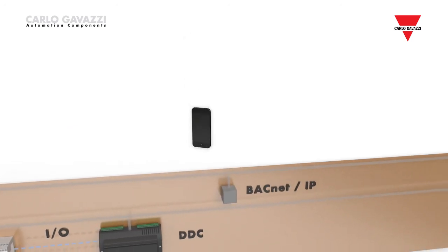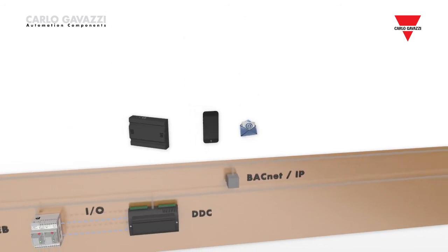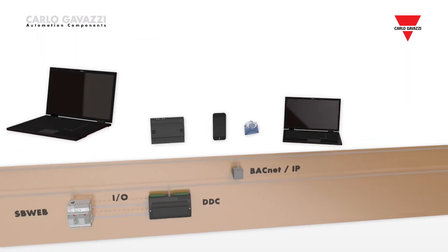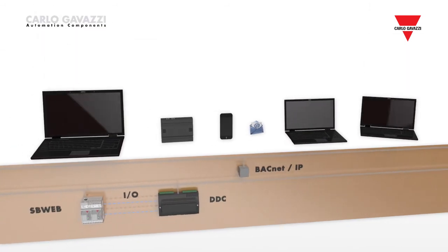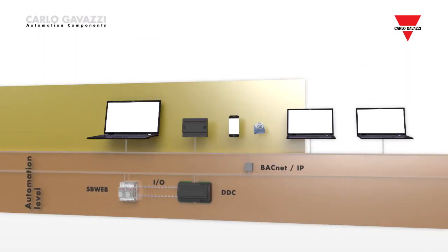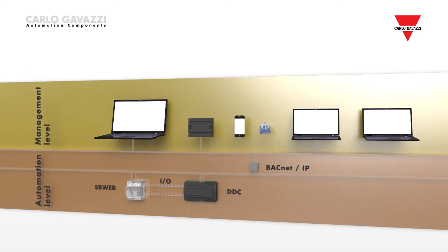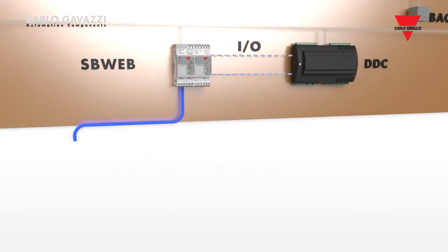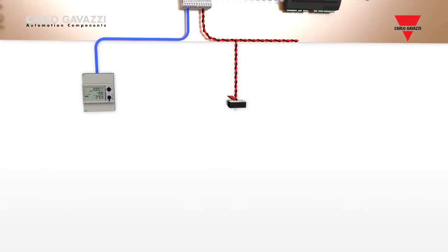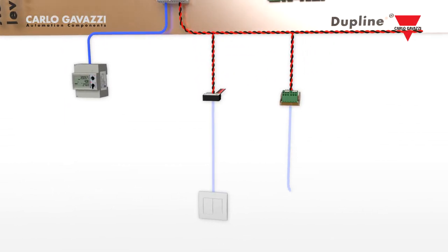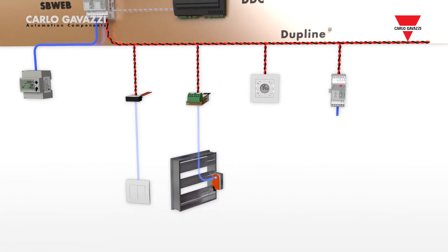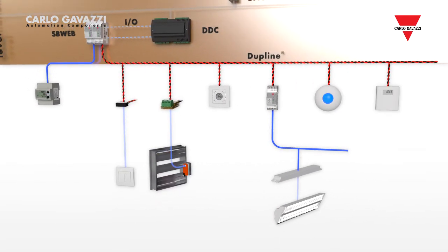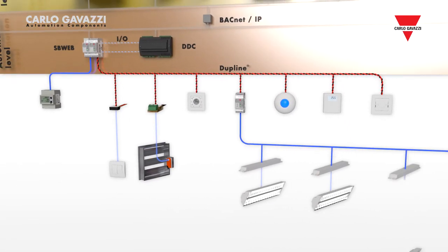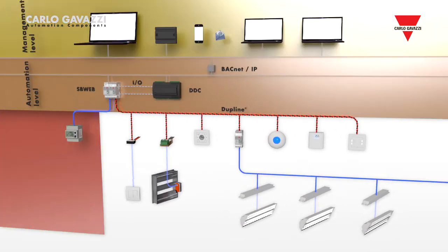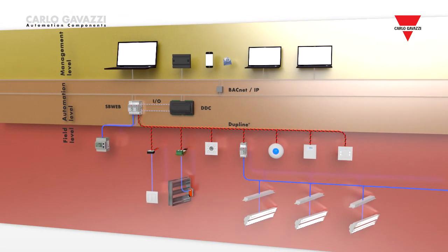With the two applications implemented in the same installation, the wiring and commissioning is much more effective and the sensor signals can be shared. A good example of this is presence detectors, which are needed for energy saving in both lighting and indoor climate control. Instead of having two presence detectors, one for lighting and one for HVAC, only one is needed in an integrated solution. This provides savings both in material and labor costs.